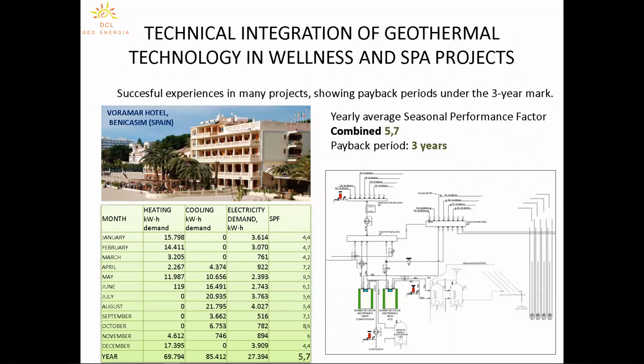With just 2 heat pumps, we have been able to provide the building with heating, cooling, conservation chamber cooling, hot water, and so on, replacing the existing cooling systems and gas boilers. The combined seasonal performance factor has been 5.7, which is a very outstanding figure. We achieved that by combining the production of heating and cooling with just one system. The payback period has been just 3 years for the investment.